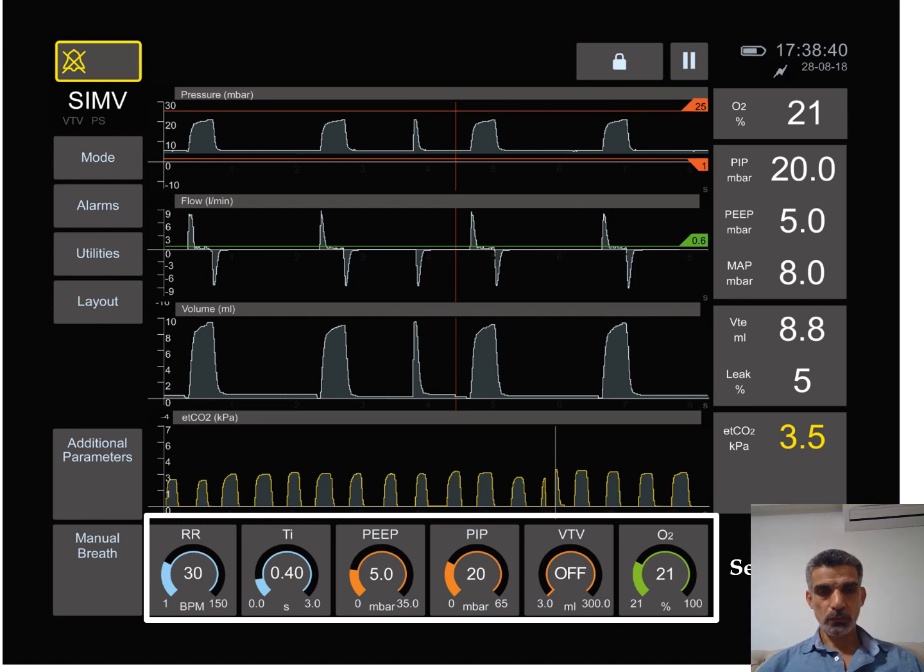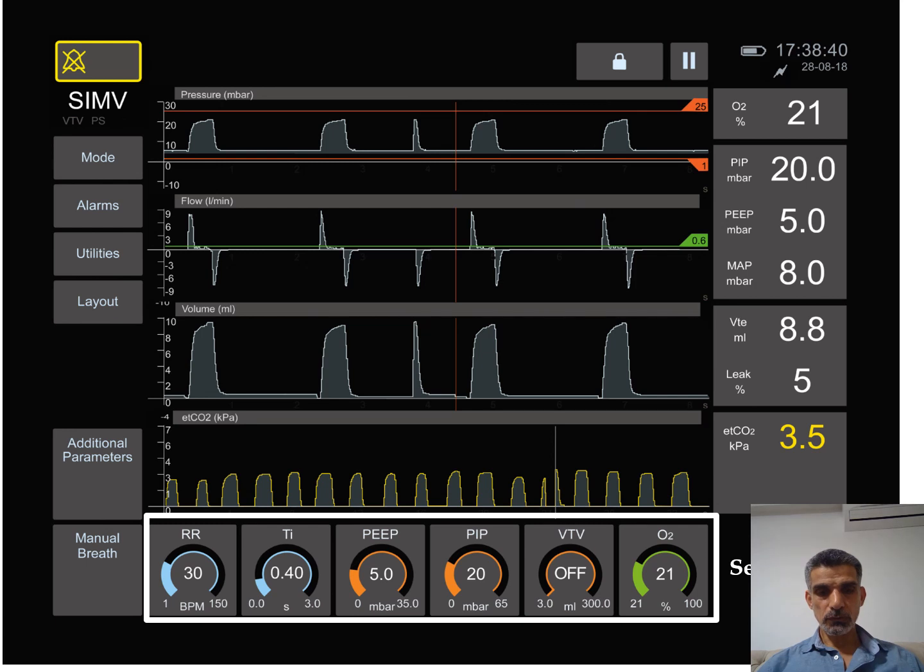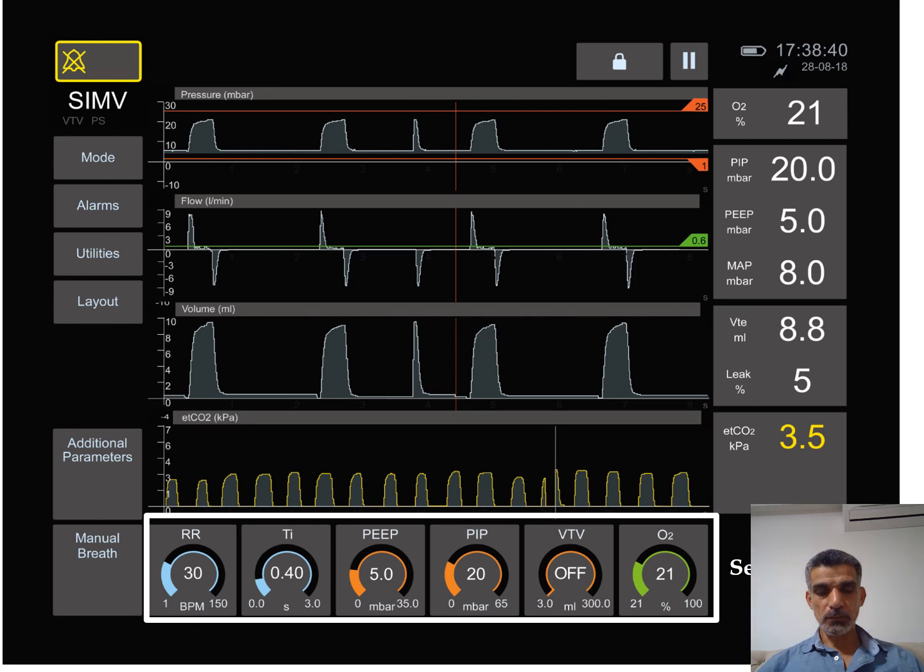We also tell the ventilator what is the PEEP, which is the pressure applied to the respiratory cycle during the whole respiratory cycle, inhalation and exhalation. It's the pressure needed to maintain the alveoli open during exhalation and it's measured by centimeter water.